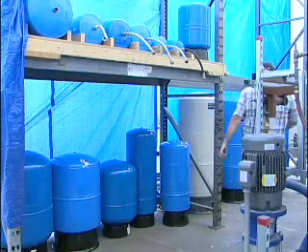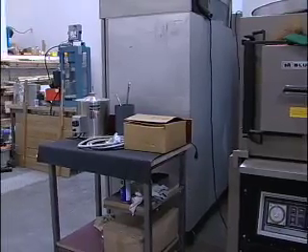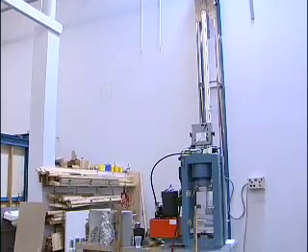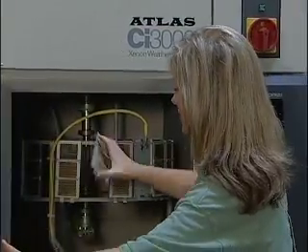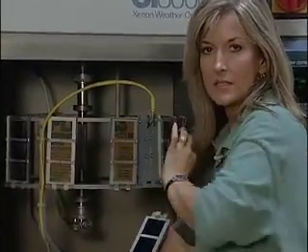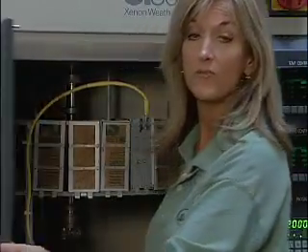When you need to ensure that your products meet or exceed a specified standard, IAPMO R&T Lab is equipped with the most state-of-the-art testing apparatuses including loading on various plumbing fixtures and fittings, toilet volume and flow dynamics against the standards with different types and volumes of media. The Xenon Arc Accelerated Aging Unit ages plastics like the kind you would find in your bathtub, your countertop or your sink. Inside, a xenon light sends out a very powerful pencil-thin light that simulates the natural fading of plastics exposed to natural light over time.